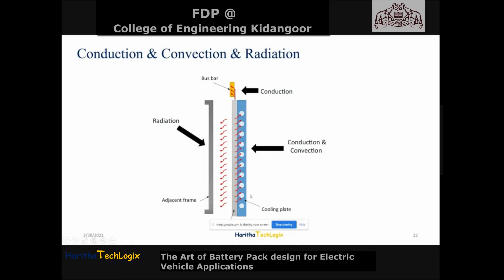The operating temperature of a battery pack system can range from minus 20 degrees Celsius to plus 45 degrees Celsius. This is the operational temperature, but the optimal range for better battery pack functioning is 10 degrees Celsius to 35 degrees Celsius. Below 10 degrees Celsius, the heating system will turn on, and above 35 degrees Celsius, the cooling system will turn on to bring down the temperature. The extreme temperature range a battery pack can survive is minus 40 degrees Celsius to plus 60 degrees Celsius, the maximum they can handle properly.